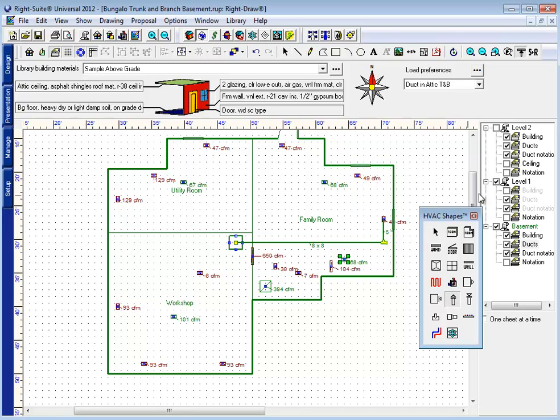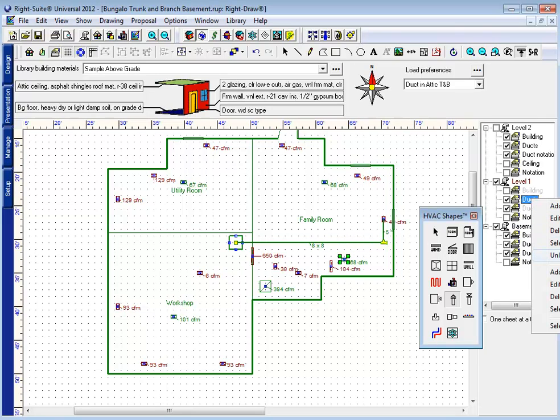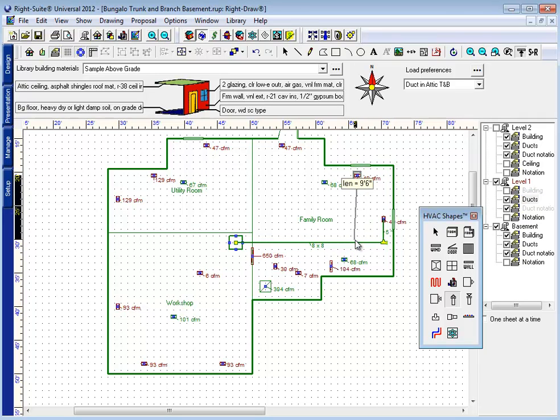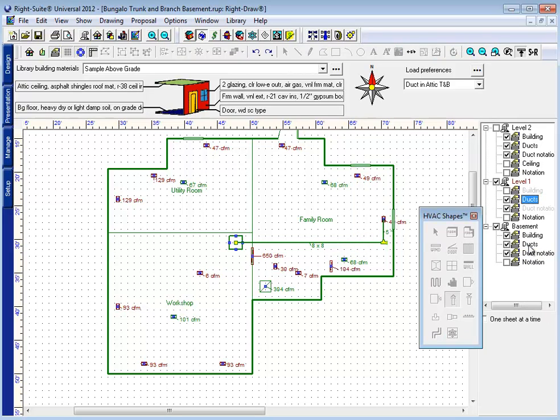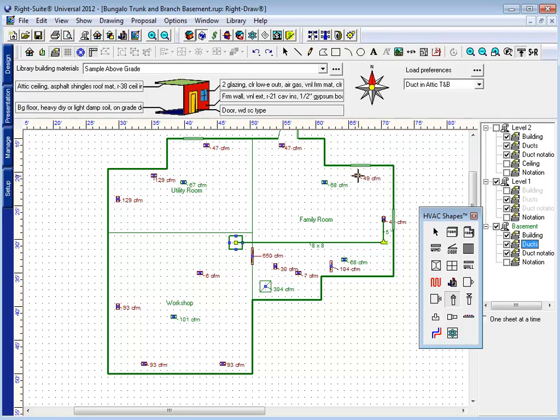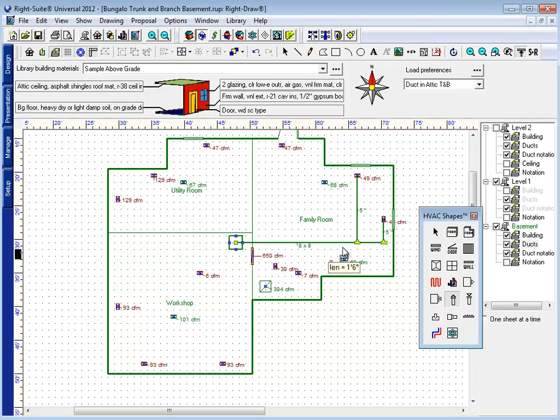So if I draw a branch on my level one and the trunk in my basement, and you see I have to unlock that to make that happen at this point, the program won't connect that duct. See it needs a riser there to get to level one. So all I need to do is make sure that all of the ducts that I draw stay in my basement, and I can connect to those level one registers without any issues whatsoever.